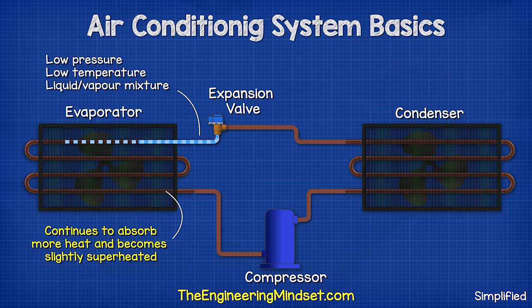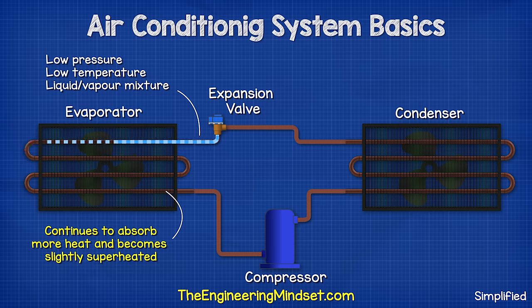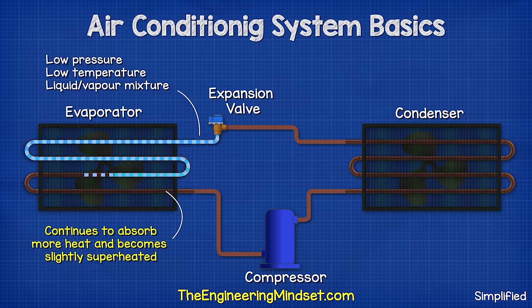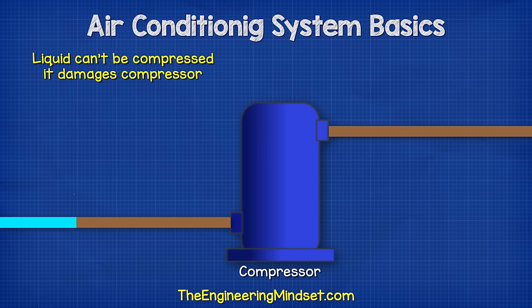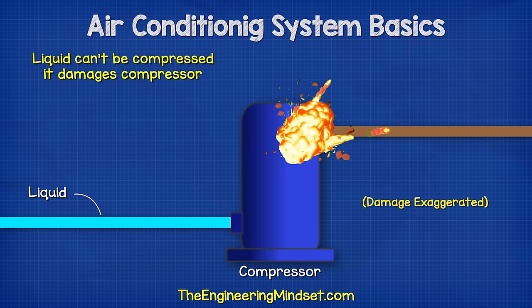The refrigerant continues to travel through the evaporator, picking up more heat, which boils it further until it becomes slightly superheated. This basically means it's now completely gas, and doesn't contain any droplets of liquid refrigerant. Liquid damages the compressor, so we want to ensure it can't reach the compressor.